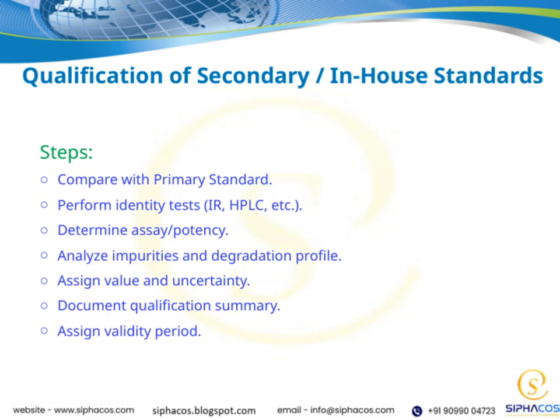Documenting a qualification summary is essential. This provides a clear record of all the tests and results, supporting traceability. We then assign a validity period, indicating how long the standard can be confidently used before requalification is needed. Throughout this process, careful qualification of secondary or in-house standards ensures the consistency and integrity of our analytical work, maintaining high quality in all our testing procedures.